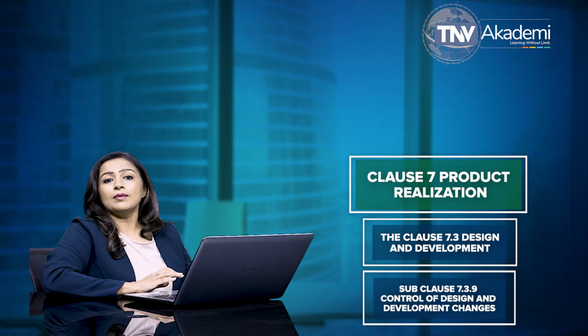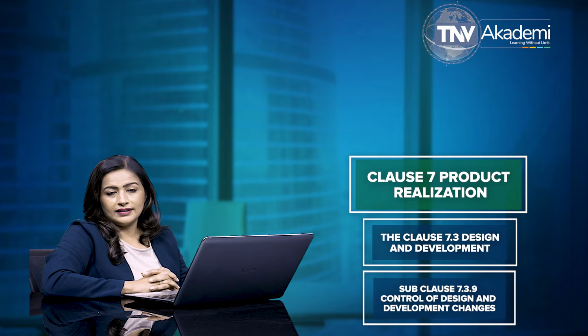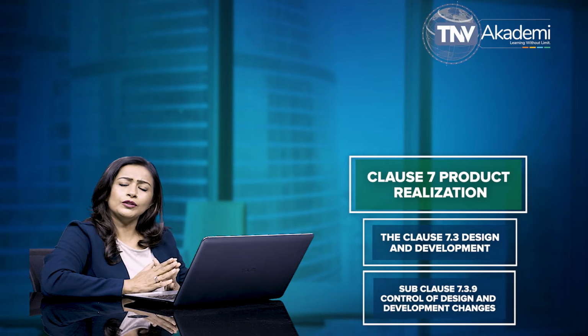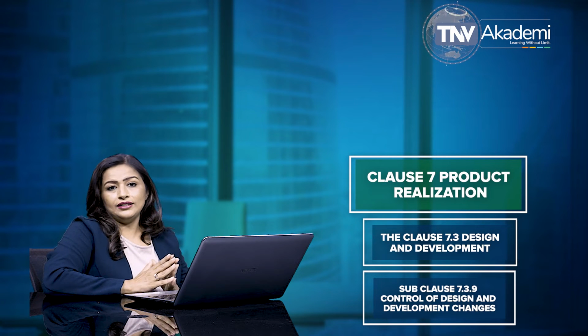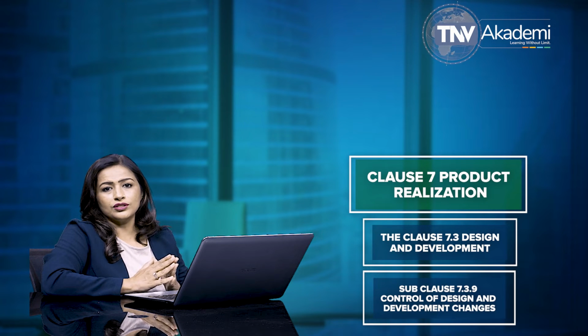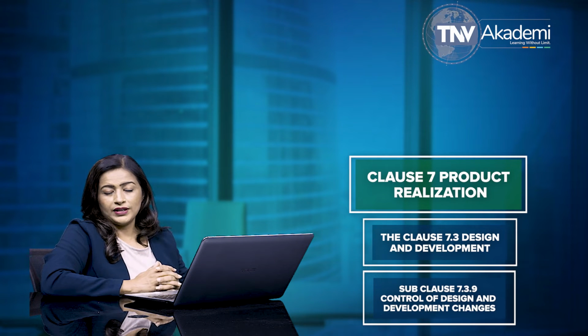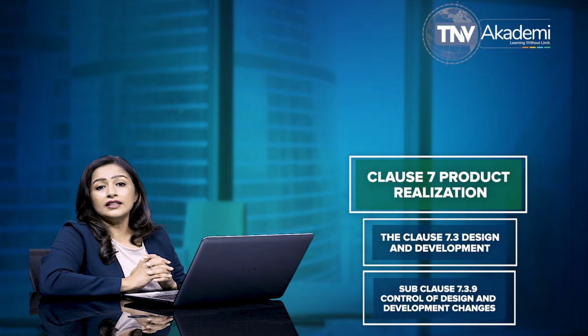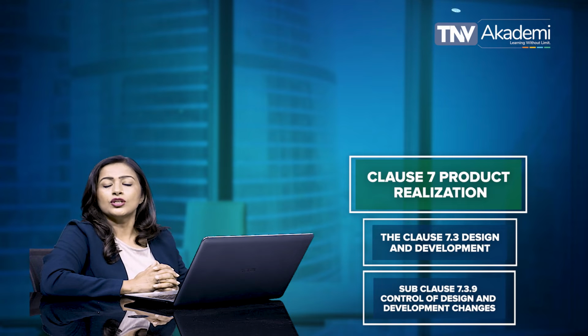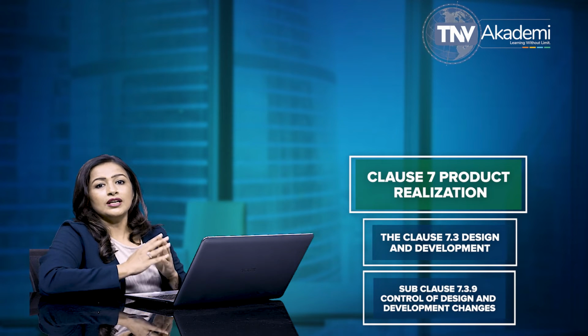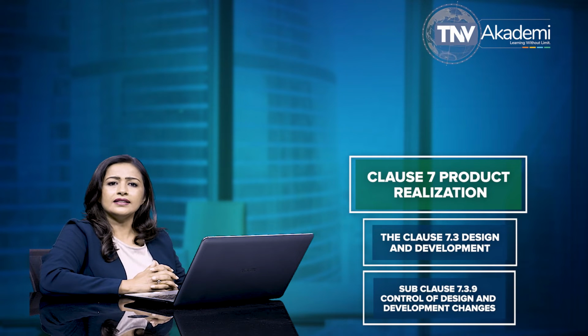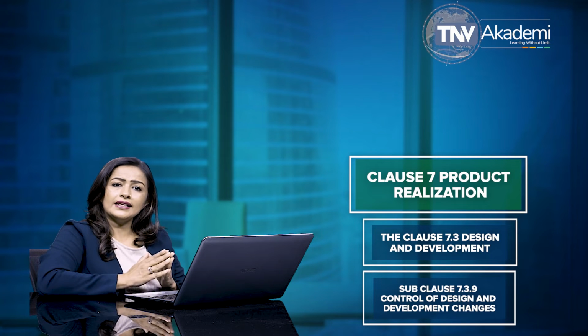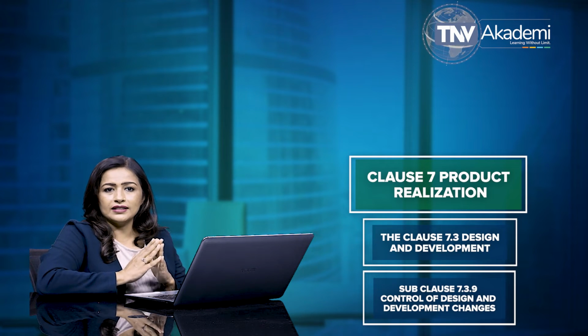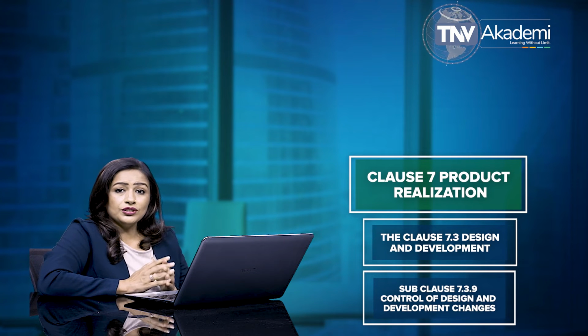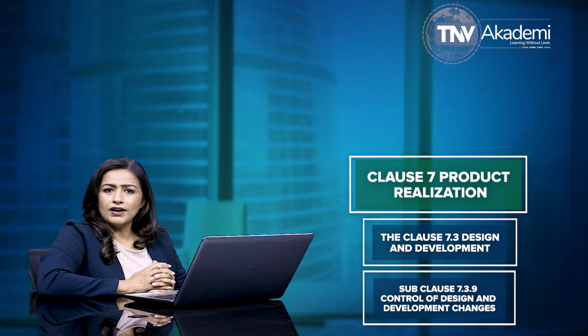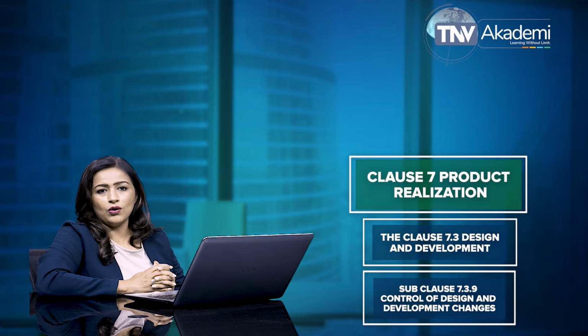Now, coming to subclause 7.3.9, Control of Design and Development Changes. Subclause 7.3.9 specifies that the organization is required to document procedures to control design and development changes. The organization is required to determine the significance of the change to function, performance, usability, safety, and applicable regulatory requirements for the medical device and its intended use. As per this subclause, design and development changes are required to be identified. Before implementation, the changes are required to be reviewed, verified, validated as appropriate, and approved by the organization.